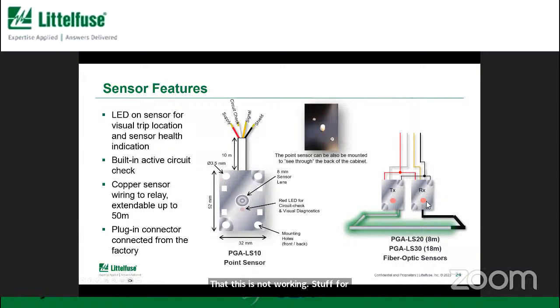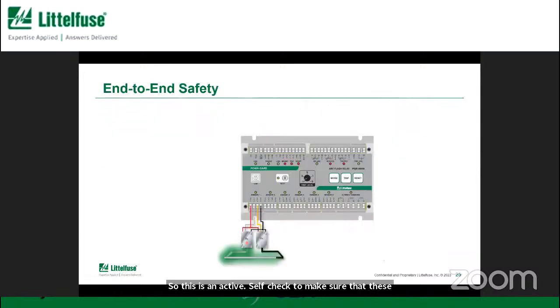Now for the fiber, it's a little different, but we inject a small light down the fiber that is measured at the receiver, and again, we confirm that's a correct test signal. So we're verifying the fiber itself. We're also verifying the electronics in these transmitter and receiver boxes. So this is an active self-check to make sure that these sensors are operating as you expect. So that's the first part of the self-check system.